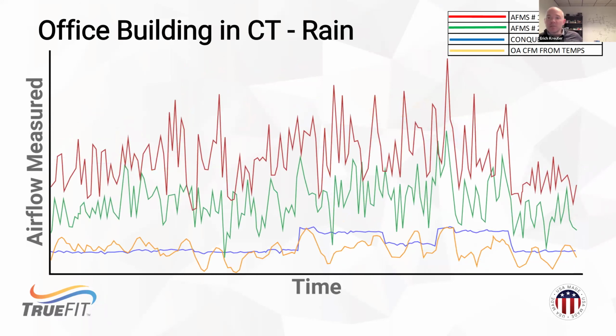So this was the same system during a period of rain. Typical OA would be designed at a low enough velocity that we shouldn't be pulling in contamination and moisture and things like that. Especially with thermal dispersion, even with temperature sensors, anything that affects that thermal mass equation is going to affect the quality and repeatability of their measurement. I think anybody that's done OA measurement with thermal dispersions, like in a hood of a rooftop, has probably seen charts that look like this already.